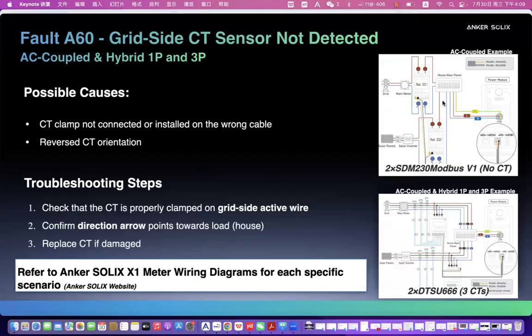Okay, so from the fault part, we have some codes, and most frequently they relate to communication, especially from the beginning, A60. It's about the grid-side CT sensor not detected. What does this mean? It normally happens with our grid-side meter. We have some CT version meters, and sometimes at the grid-side the CT clamp is not connected in the correct phase. For example, AB phase wrong or wrong orientation, where the detection is not from the grid point to the home loads. These issues will happen. So what are the troubleshooting steps for this part?